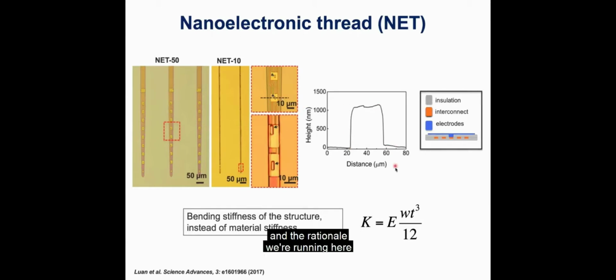And the rationale we're running here is that the flexibility of such a device is determined by the bending stiffness of the structure. And the bending stiffness, if you look at the equation, is proportional to the Young's modulus and also t to the third, the cube of thickness. So if we switch the material of the probe from rigid materials such as silicon and metal to polymers, we gain a lot in terms of flexibility. But a more effective modulator here is the thickness of such a device.